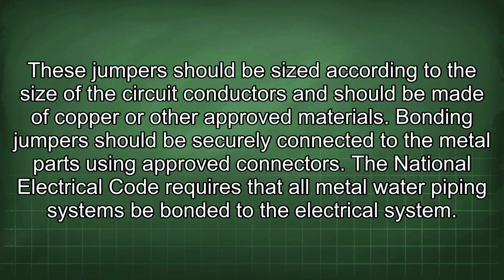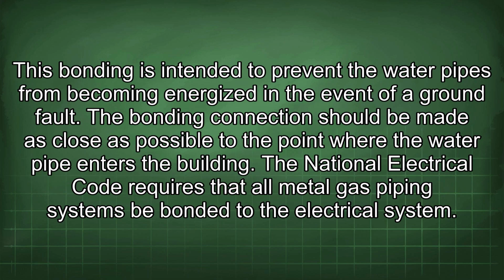The National Electrical Code requires that all metal water piping systems be bonded to the electrical system. This bonding is intended to prevent the water pipes from becoming energized in the event of a ground fault. The bonding connection should be made as close as possible to the point where the water pipe enters the building.